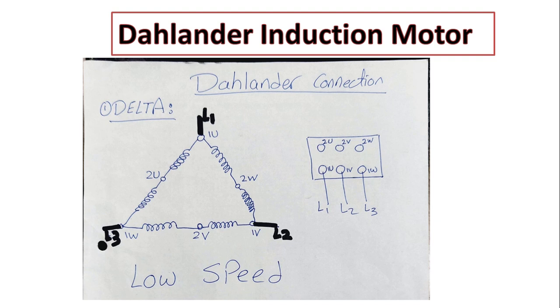As you can see, here is the motor connection from inside and this is our junction box. If we connect the power supply L1, L2, L3 to 1U, 1V, 1W, it's connected L1 to 1U, L2 to 1V, L3 to 1W. This is a delta connection which has the low speed feature.